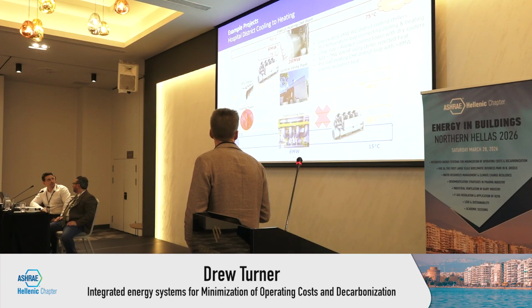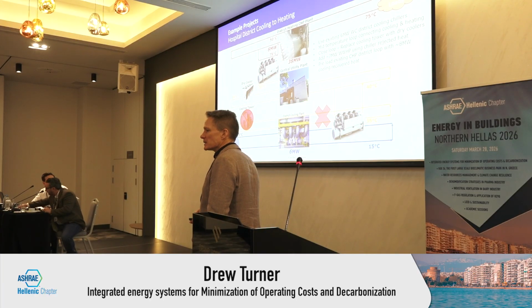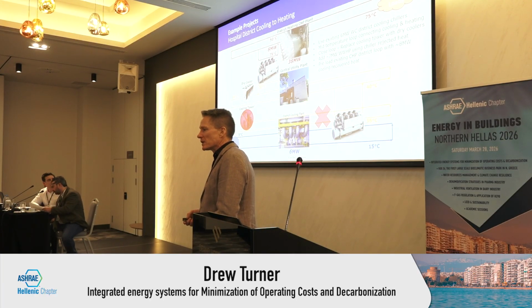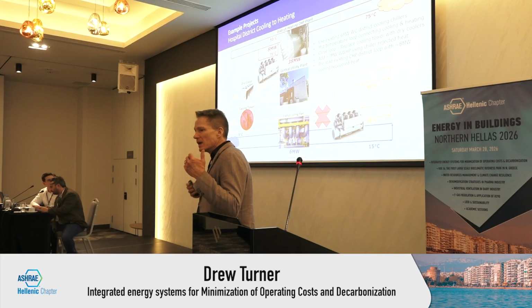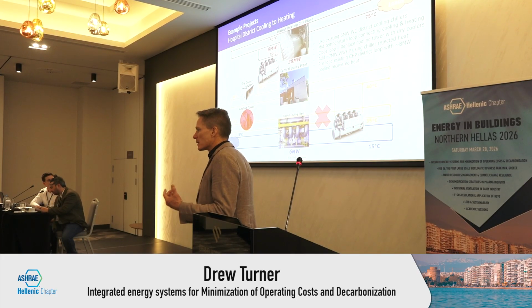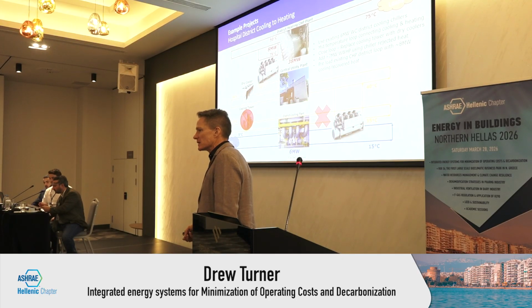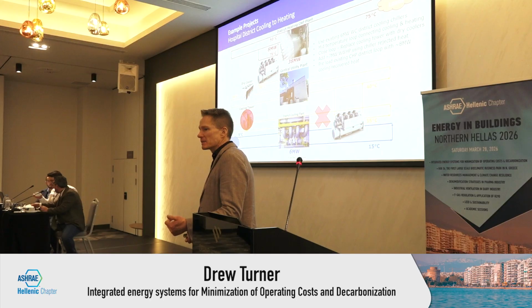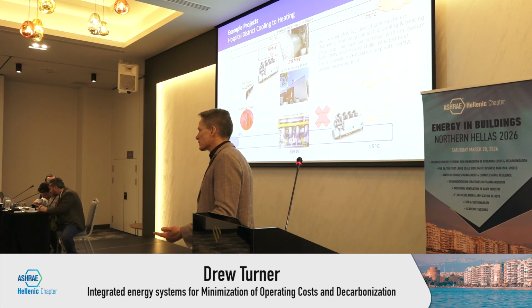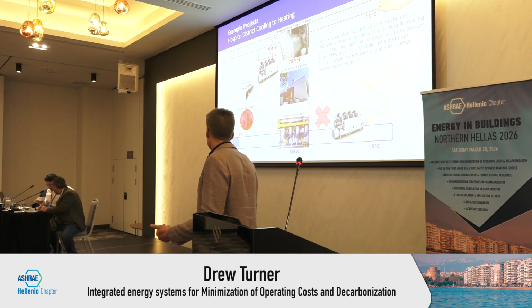So this was the retrofit. One of the other points we make is: close the loop. What do we mean by that? If you're rejecting heat through cooling towers and dry coolers, that's the first thing we look for. If a critical facility has cooling towers, that's your target, that's your source. No energy should be rejected in the future if you have heating load at the same facility—you don't need those cooling towers anymore, or just keep them as backup, same with dry coolers.